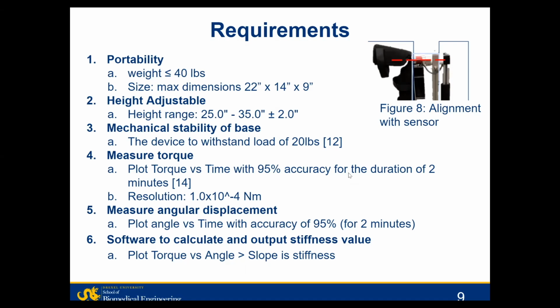Because in order to accurately assess the patient, they must lay flat on the table, ideally a medical table, and the height adjustability allows the user to align the sensors with the patient's elbow joint. And most tables have a height between 25 to 35 inches.